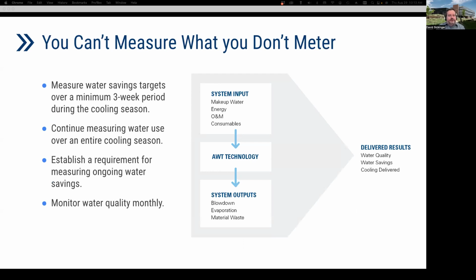Mentioned before is that you do want to establish a solid baseline before an AWT system is installed. To achieve that, I recommend a year's worth of records is ideal. However, meter data over a single cooling season is usually sufficient. When you are measuring water savings, you want to do that over a minimum 3-week window of continuous operation, and then preferably track performance over an entire season, as conditions can change over a season. Monitoring water quality monthly reports, including coupon stations to detect any changes, so it gives you time to correct if needed.